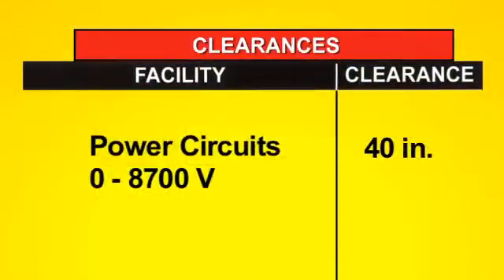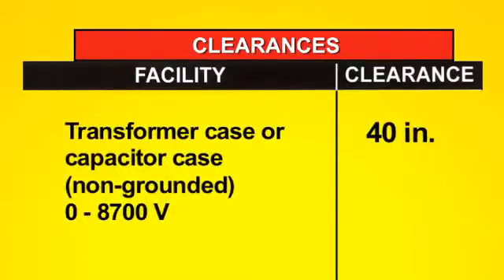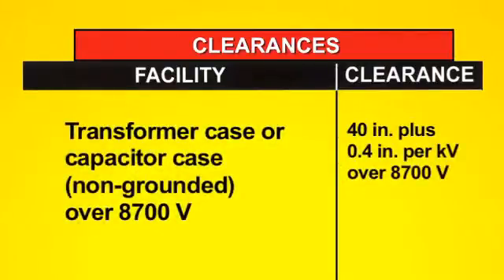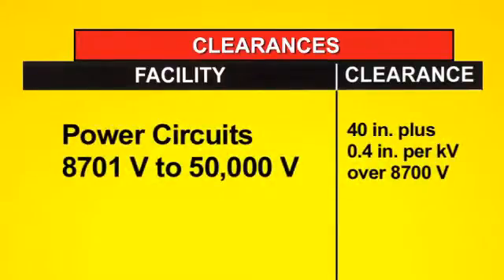This chart describes necessary clearances on joint use poles. On power circuits of between 0 and 8700 volts, the minimum clearance is 40 inches. For transformer cases or capacitors that are not grounded, the minimum clearance is 40 inches. For transformer cases or capacitors that are grounded, the minimum clearance is 30 inches. For transformer cases or capacitors over 8700 volts that are not grounded, the clearances are 40 inches plus 0.4 inches for every 1000 volts over 8700. For power circuits of 8700 volts to 50,000 volts, you can determine the safe clearance using the same formula.